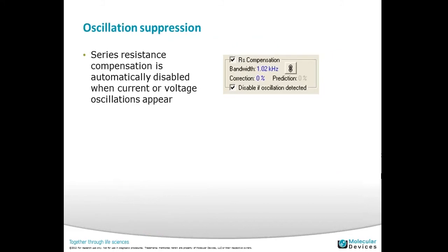Oscillation suppression is one of the good features, because in voltage clamp measurement we compensate for the series resistance, but sometimes if we overcompensate, oscillation or what we call ringing will happen. That oscillation or ringing can cause the cell to die. So in the 700B Commander, if you check these boxes, once oscillation is detected, the series resistance compensation will be disabled, to help prevent cell death or damage due to the oscillation.